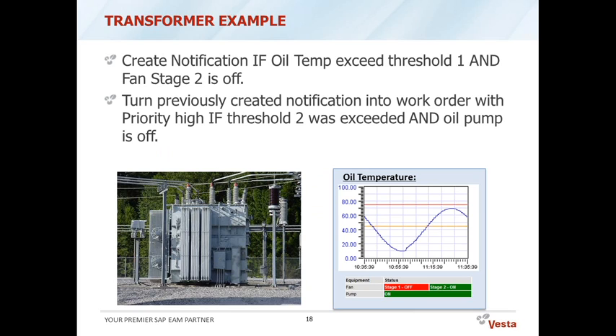Now, the situation becomes more imminent if the second or third stage of cooling is also not kicking in. So if we're exceeding yet another threshold and the oil pump, for example, which is the last stage of the cooling cycle, is not kicking in, that's when we want to certainly raise the stakes, maybe create a work order and send out an email to the responsible maintenance group to say, you need to take care of that transformer because it's about to have a sizable impact on the grid itself, but also on the long-term viability of that transformer.